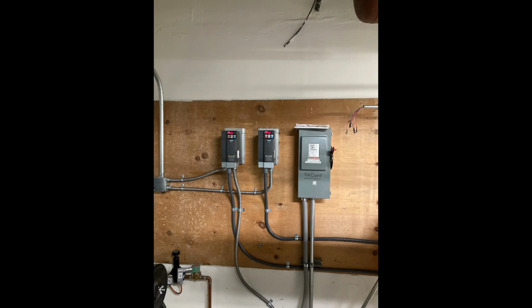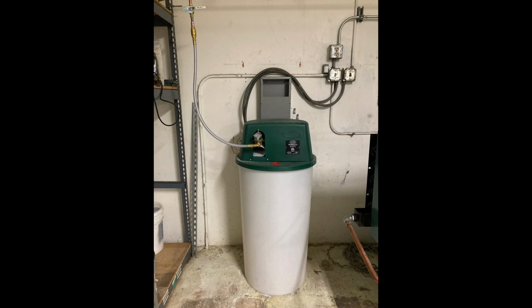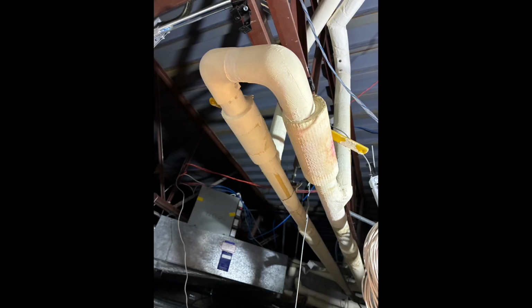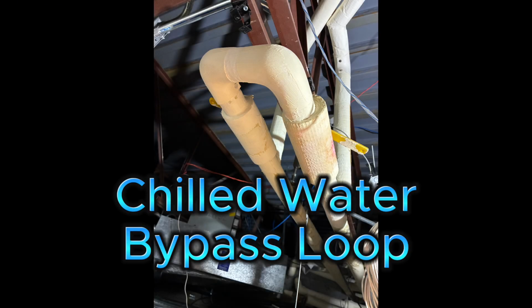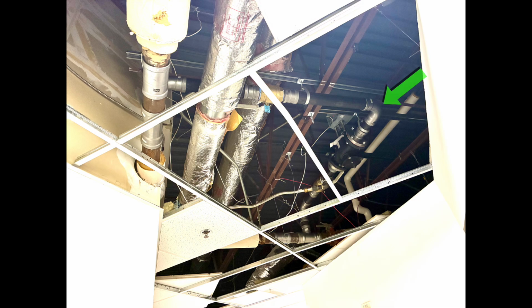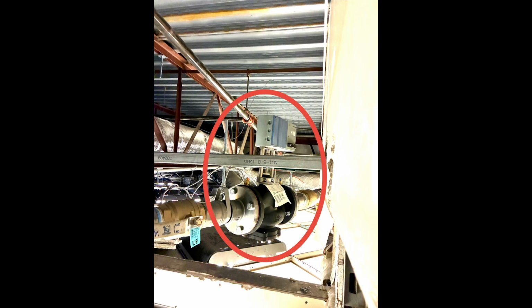And these pumps are controlled by variable frequency drives, so more energy efficient. We also installed a glycol feed tank, because here in Colorado it gets cold. And the bypass on each of the floors was too small. So we need to install newer, larger diameter bypass piping and valves, as you see here.